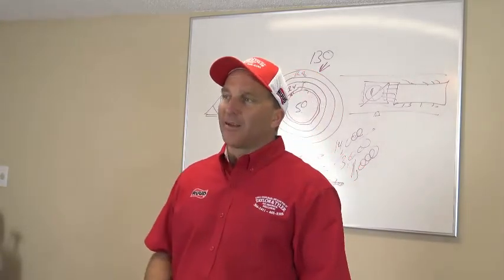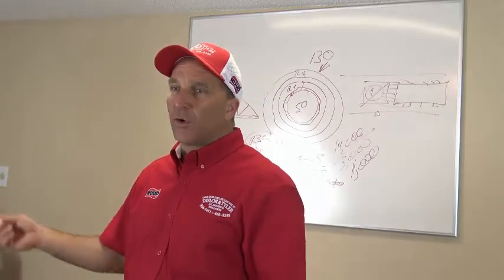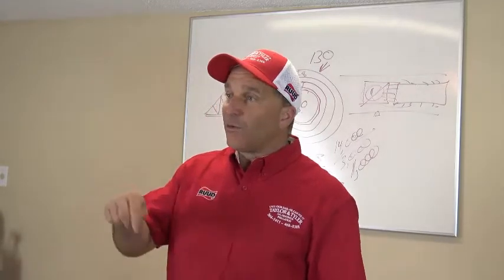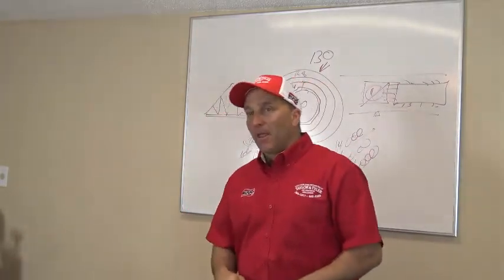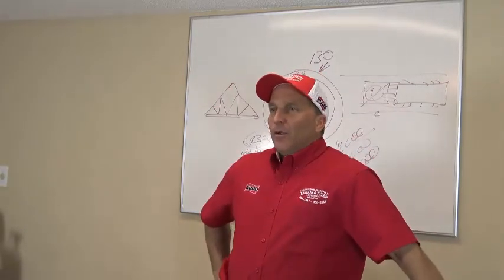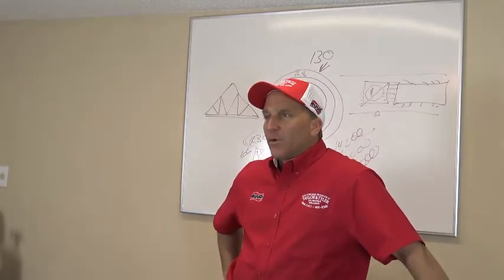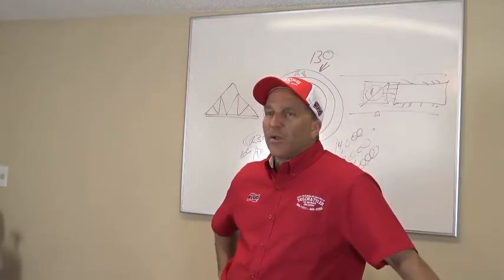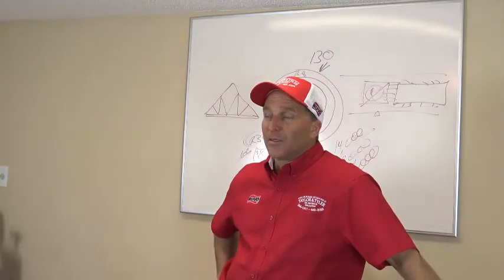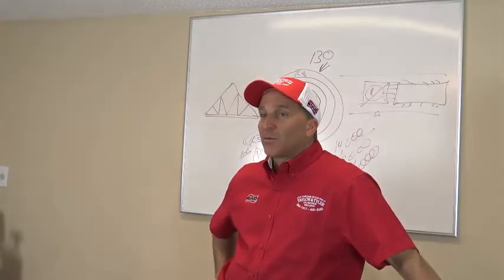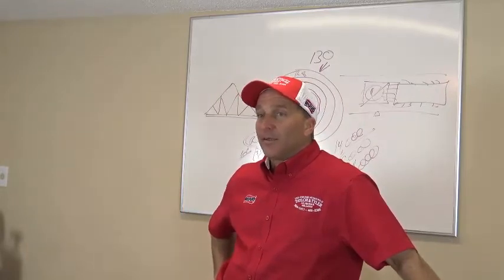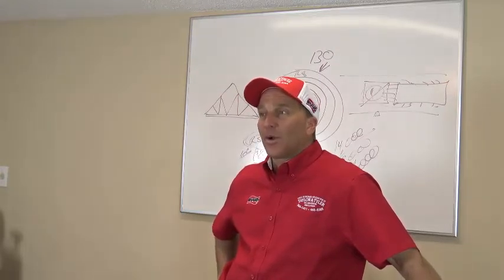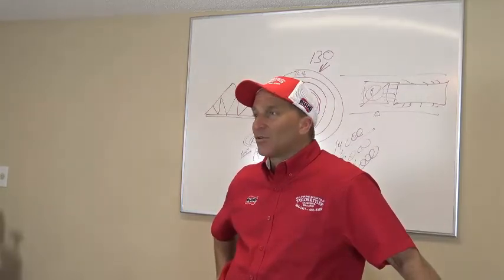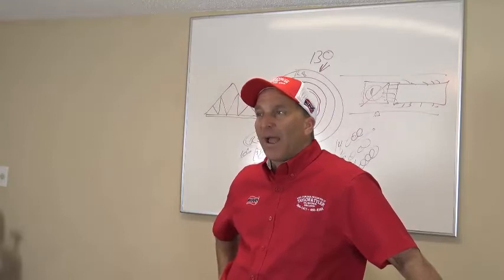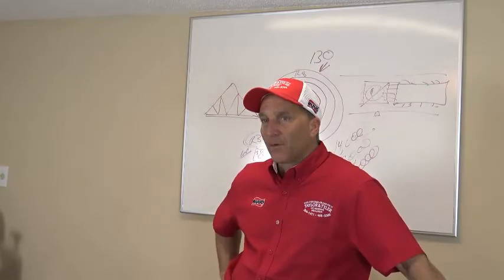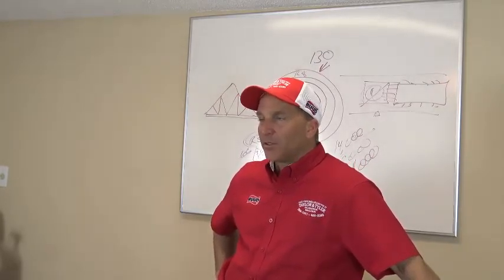You're going to look like you cleaned that condenser really good and you caused the fan motor to go out. Okay? On one of my reviews right now, it says on there, I called the owner and he told me that when they clean the condenser, sometimes the fan motor goes out. If I would have known that it was going to make the fan motor go out, I wouldn't have cleaned the condenser. Okay, so what I told him was, and of course he got it all mixed up, was sometimes when we acid wash the condenser, it changes the temperature of the motor, and it's very possible, depending upon how dirty that condenser was and how long it's been running like it is, the fan motor may go out. But it's not because the condenser's clean or we put water on it. It's because the bearings were bad beforehand and now they're running at a different temperature. Okay? And he just wanted to complain, so he goes and puts a bad review on one of the websites.